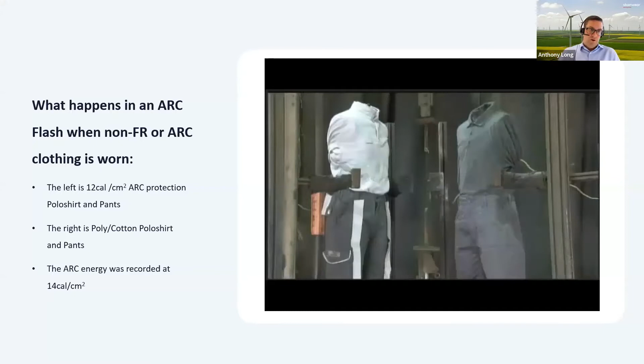So that was a 14 cal arc. You see on the left-hand side, the front of the garment is charred, but on the right-hand side, the garment's engulfed in flames. So many times we see situations whereby people haven't worn Arc Flash PPE, they've received a really bad arc, but their burns are horrendous and way, way more than the actual Arc Flash itself would have given them. And that's because the clothing is caught on fire.